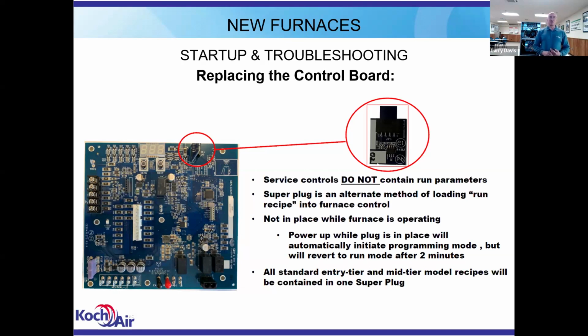Okay. So because of that, it's there. I don't recommend using it. I recommend using the app to set a board up. You don't have to be at the furnace. As long as you know that furnace serial number, you could be sitting in a McDonald's, drinking a coffee, hooked up to the Wi-Fi, and type in that serial number and program your replacement board right there. If you know all the fan speed settings and so forth, you can set it all up, have that board set, and either send it out with a technician or take it to the job site and swap it out, and you're off and running. Okay. But the super plug is there because we're required to have a way of configuring a board without being forced to use the app. All right.